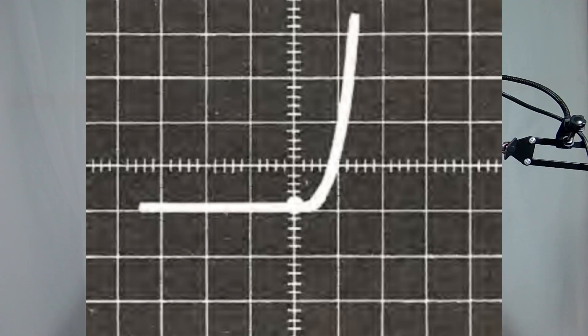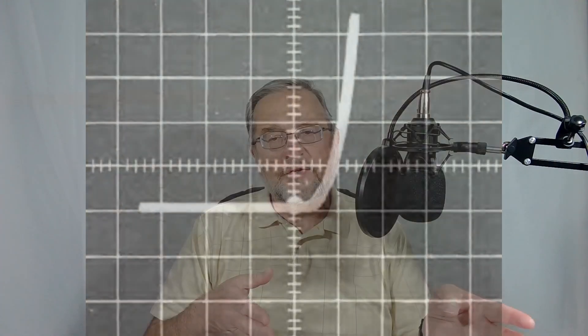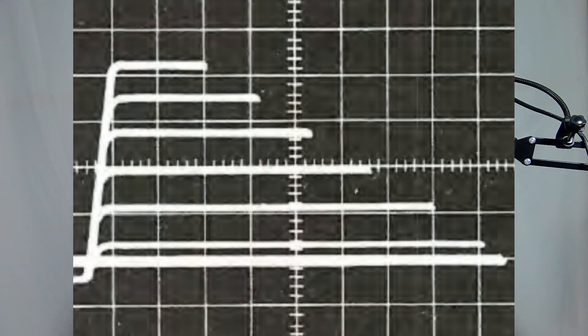Let's look at some examples of diagrams that can be obtained using a curve tracer on different components. This one is the characteristic of a resistor, which is obviously a straight line at an angle where the angle depends on the value of the resistance. This one instead is the typical characteristic of a diode — the current goes quickly up once the direct voltage exceeds the forward voltage, and the diode behaves as an open circuit for smaller or negative voltages. This one is a transistor, which gives us a whole family of characteristics based on the current flowing through its base.